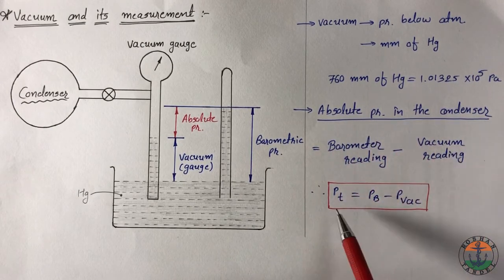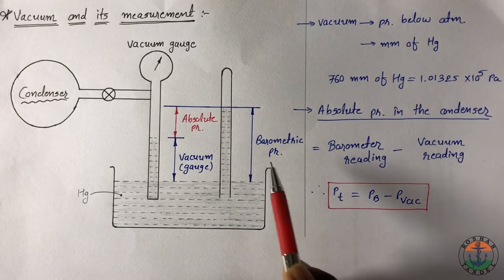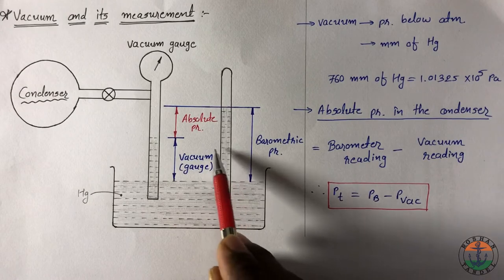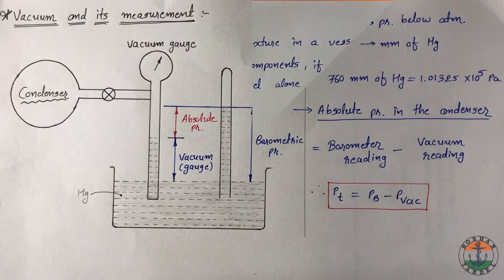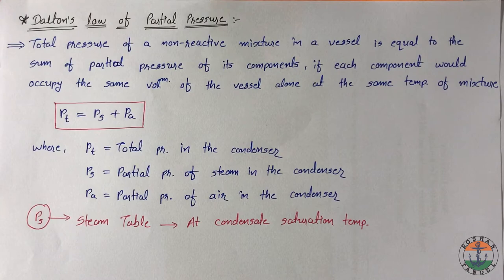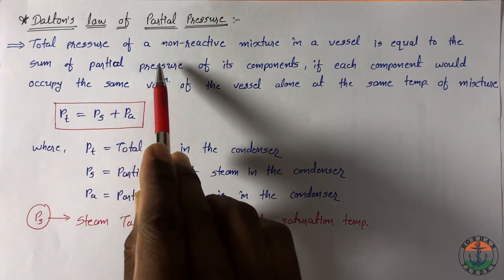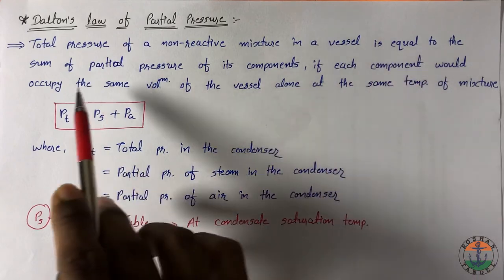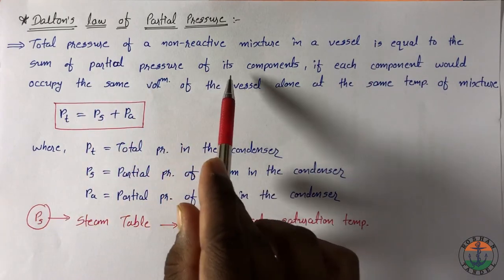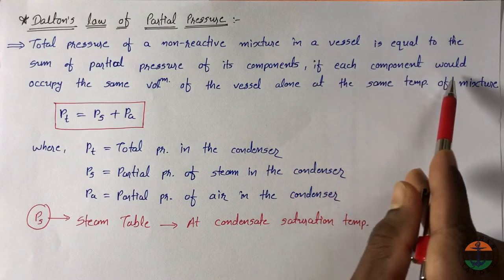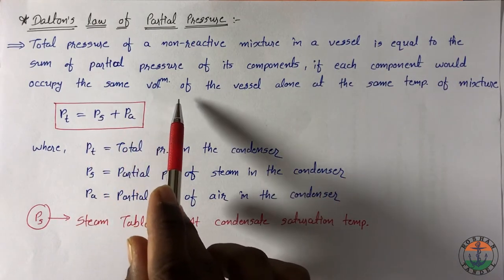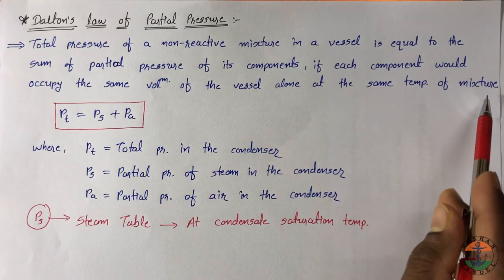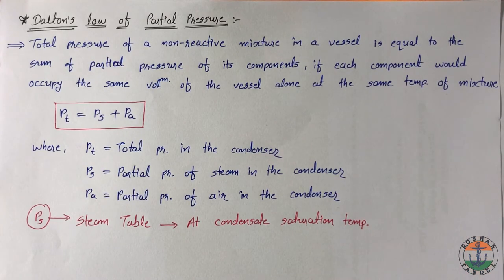Absolute pressure in the condenser Pt is calculated by barometer reading Pb minus vacuum reading. Dalton's law of partial pressure states that total pressure of a non-reactive mixture in a vessel is equal to the sum of partial pressure of its components if each component would occupy the same volume of the vessel alone at the same temperature of mixture.